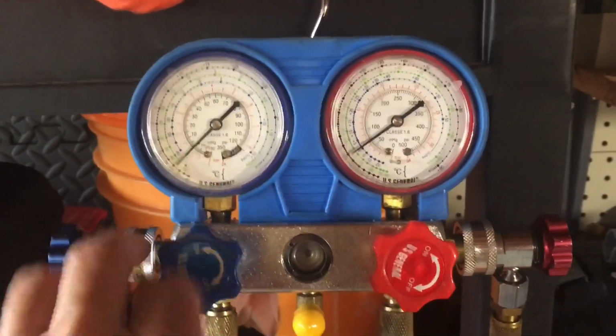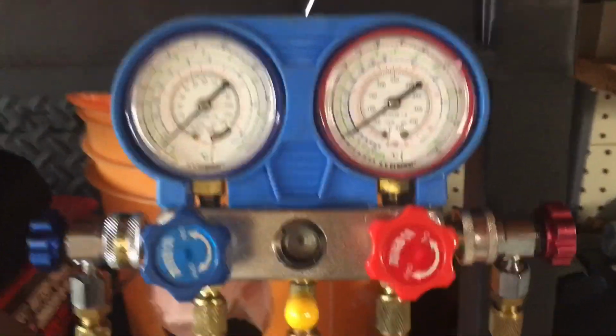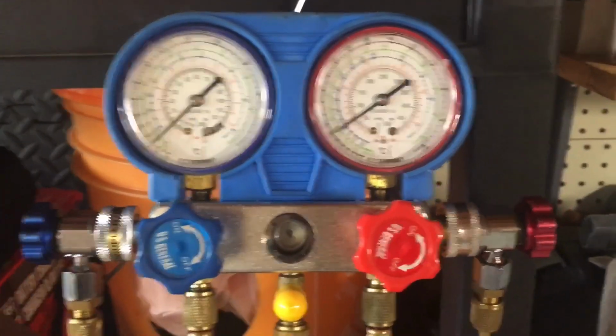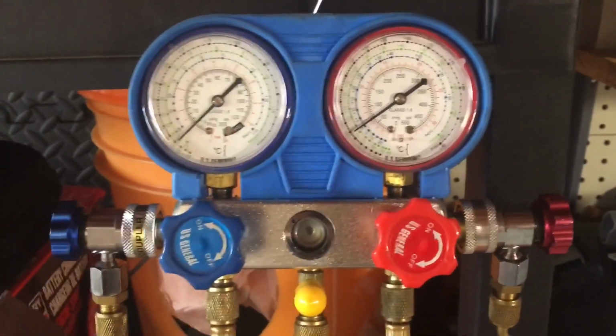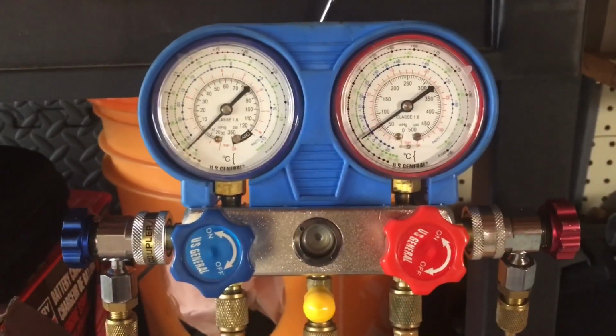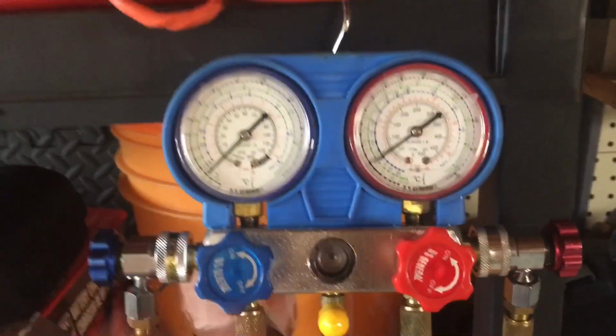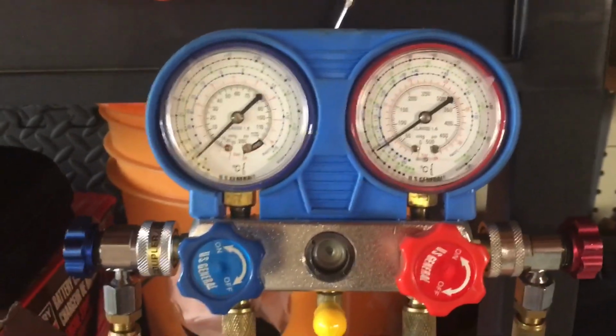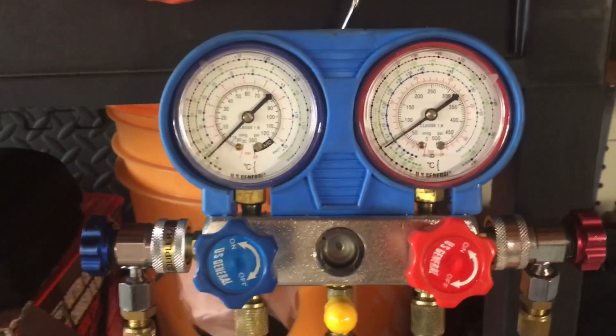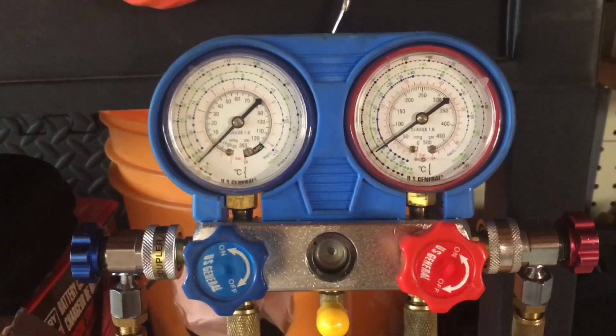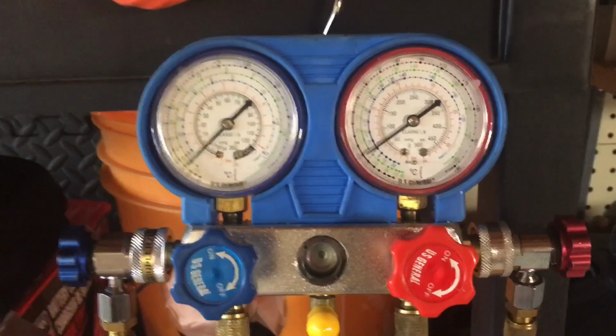Now, I mentioned in the past that anytime you've got your couplings hooked up, you're not checking the Schrader valves, because they're depressed to get access. So in order to keep your gauges hooked up and monitor the pressure, you'd need the coupling hooked up, right? Is that true? Is that 100% true? I don't think so.